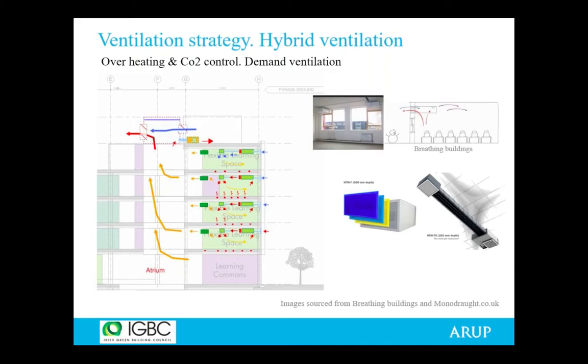the occupancy rate gets too high, CO2 sensors detect that and then supply more fresh air to lower the CO2 concentration. You can set the target to 800 or to 1000 ppm. It was mentioned in previous meetings, and if you reach that target, then you supply more air. So the fresh air supply modulates depending on the occupancy rate.